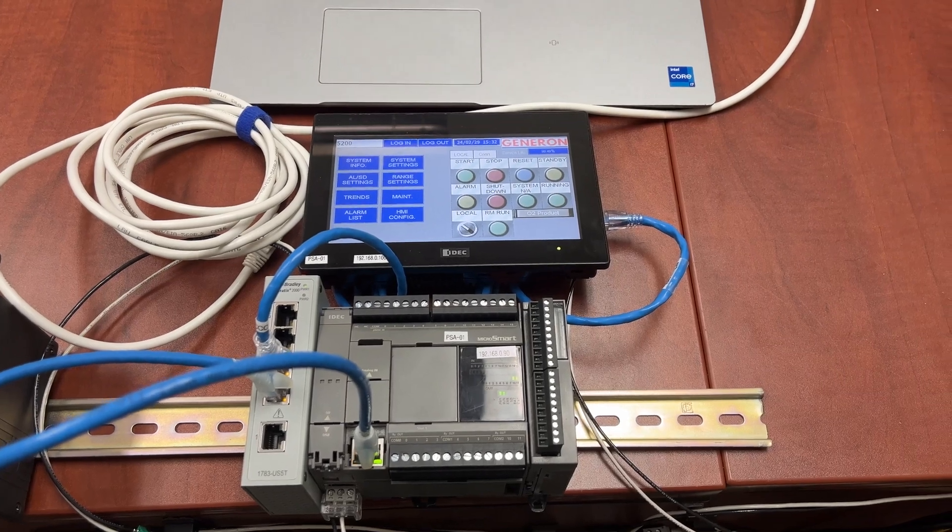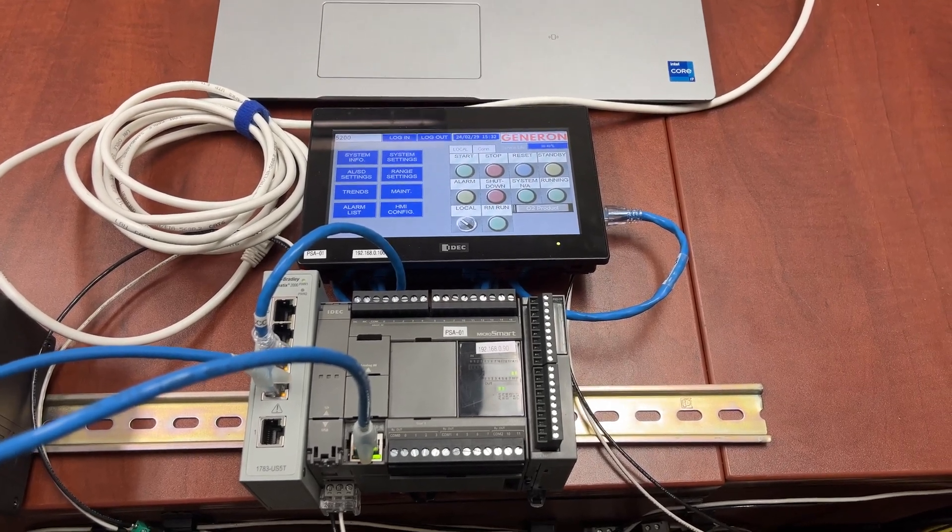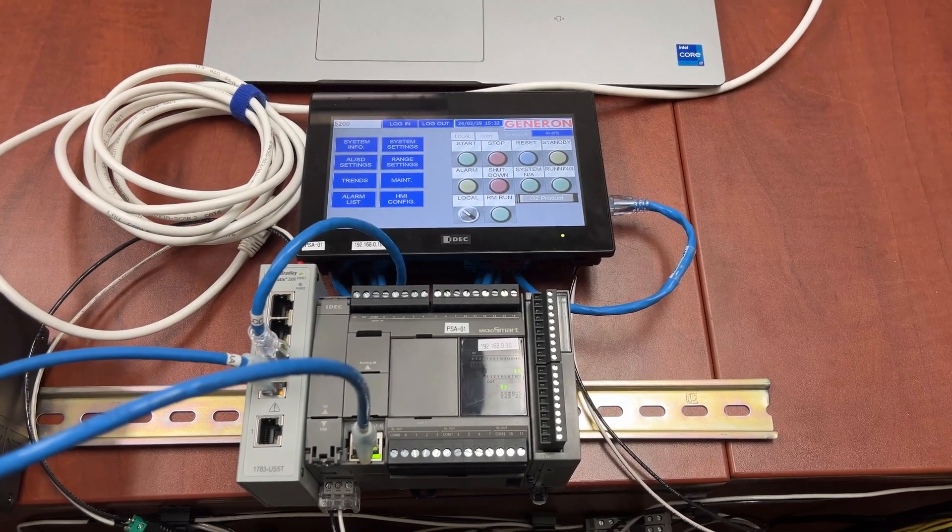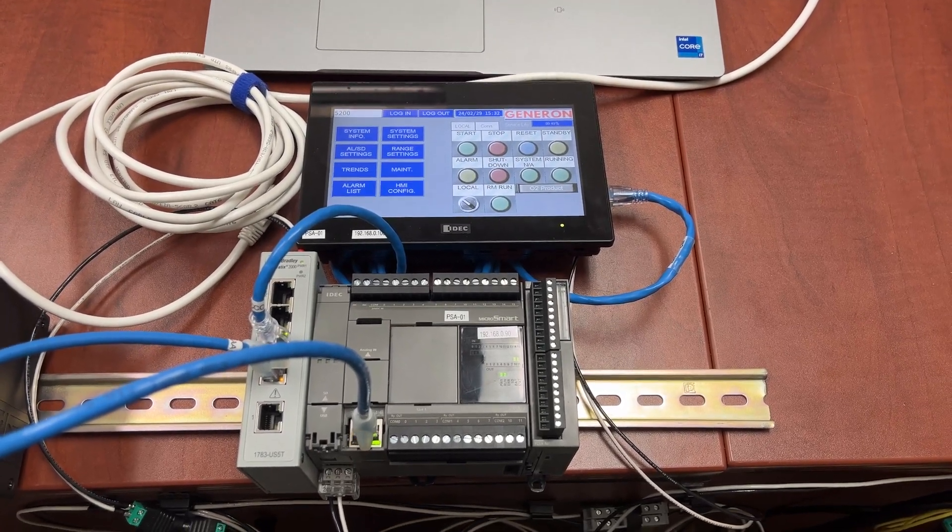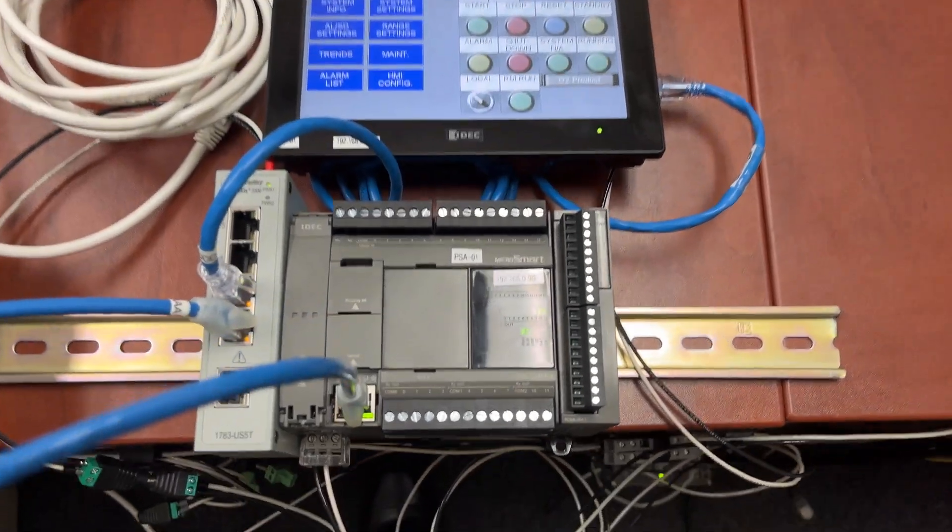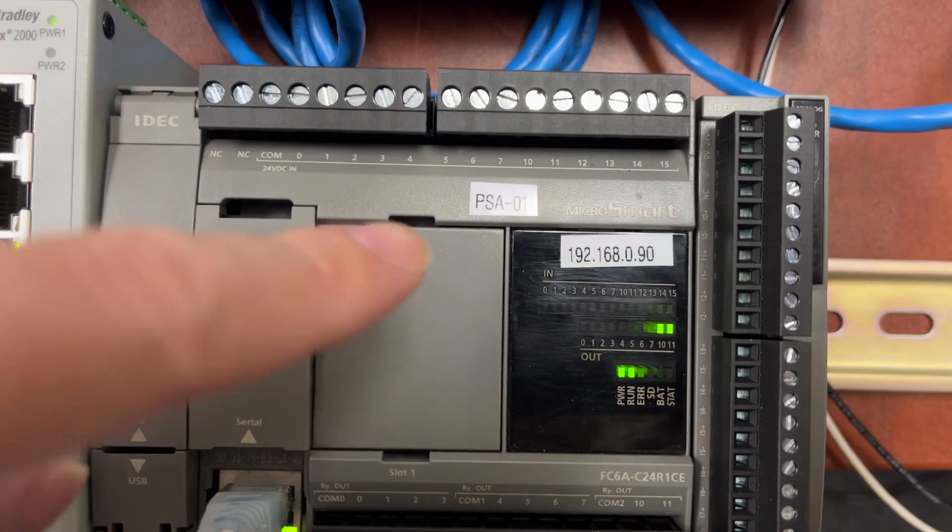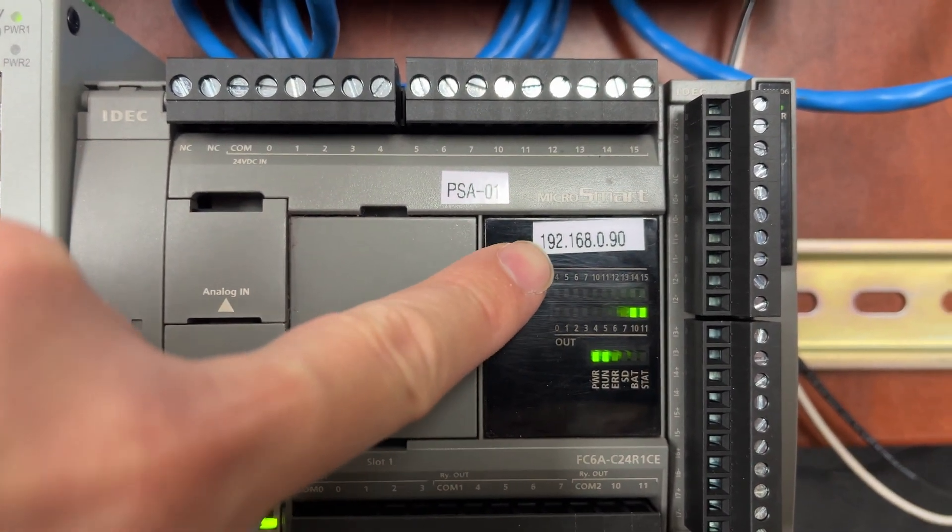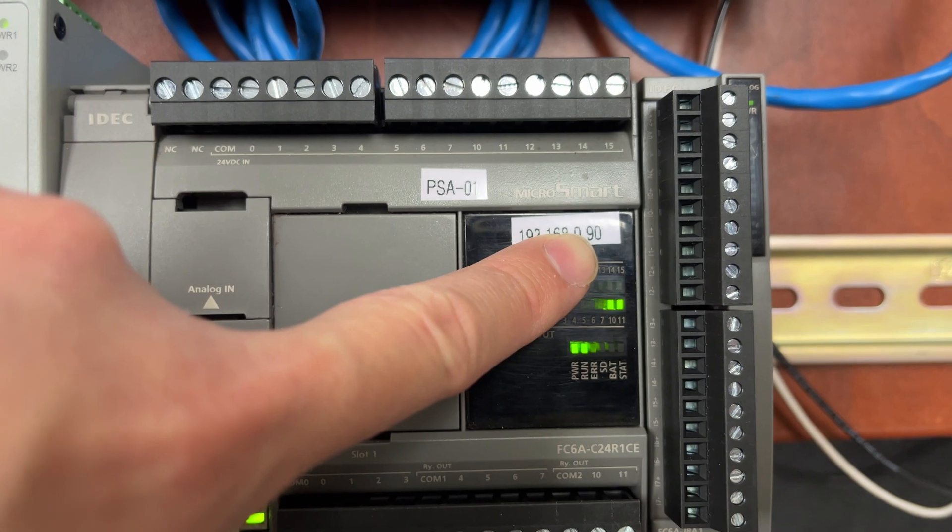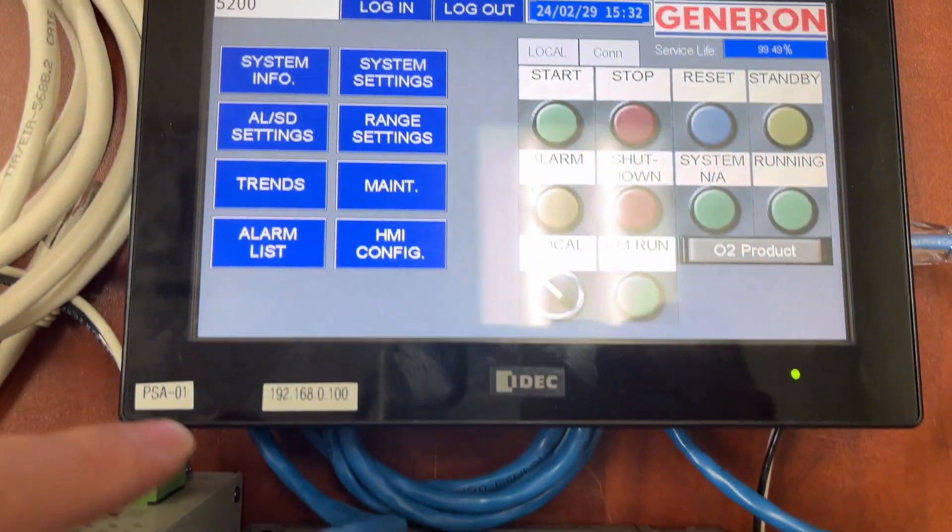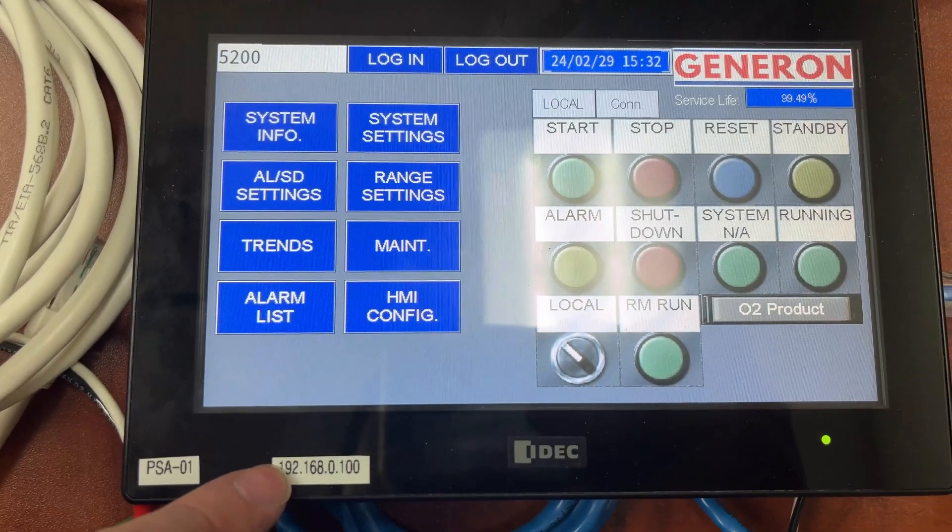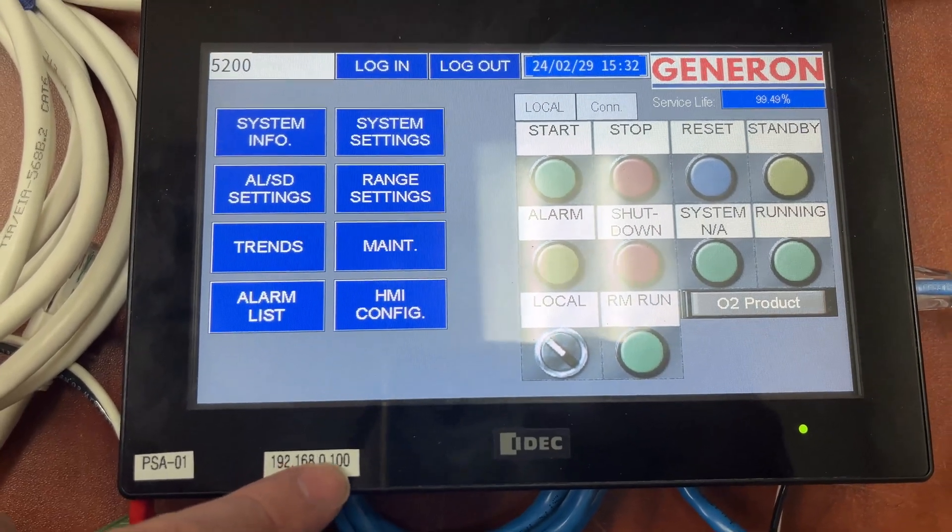The very first requirement that we need to comply with is to ensure all devices are on the same network. For the PLC, the IP address is 192.168.0.90. For the HMI, the IP address is 192.168.0.100.